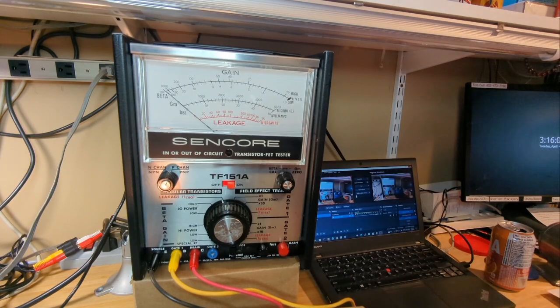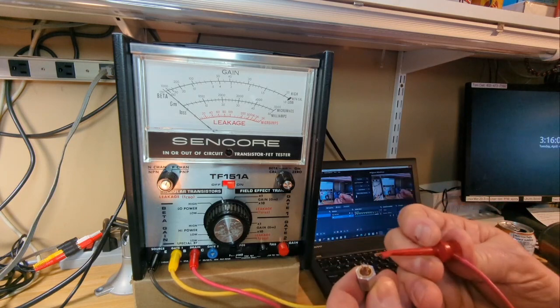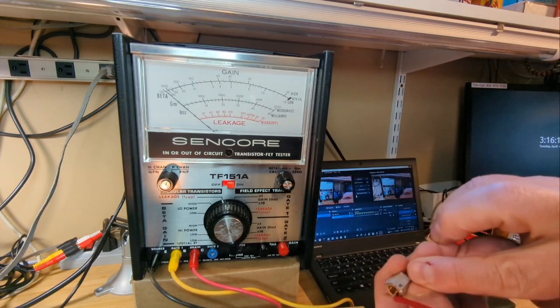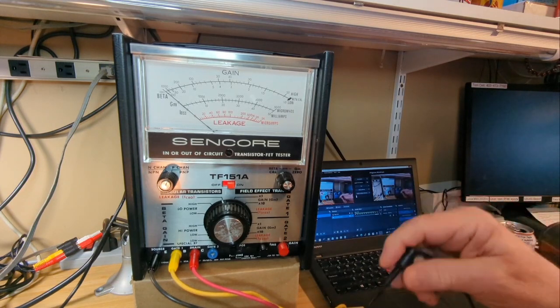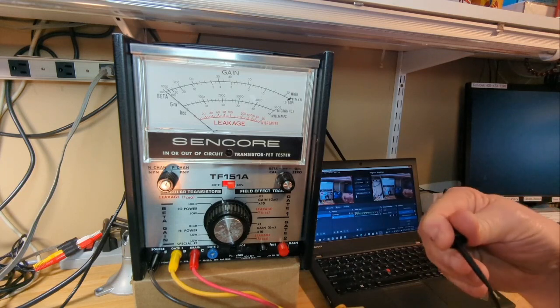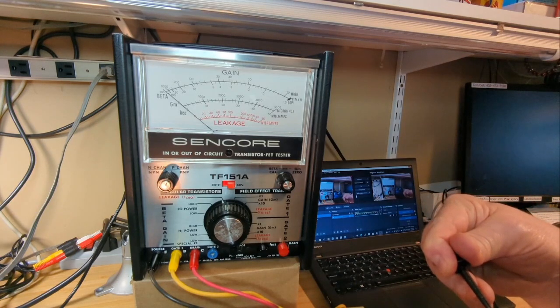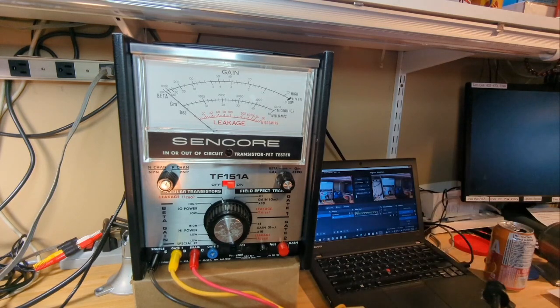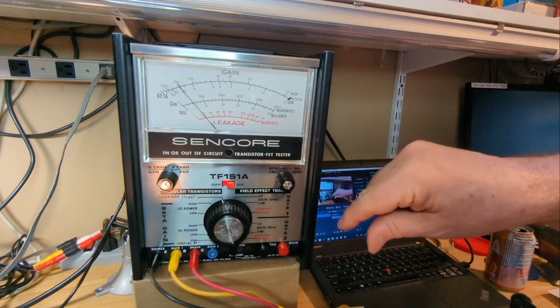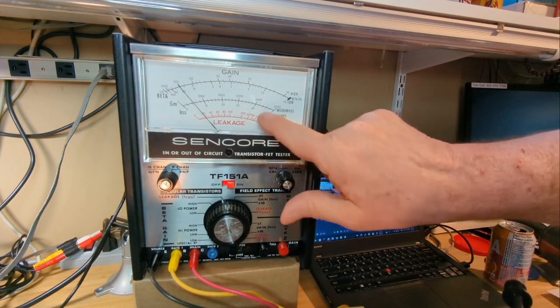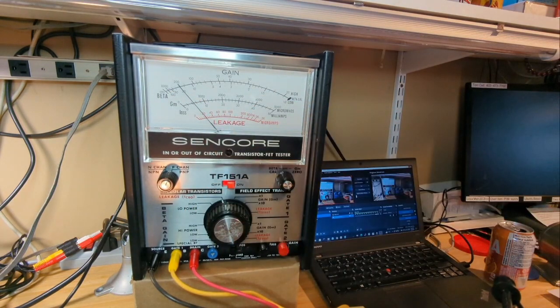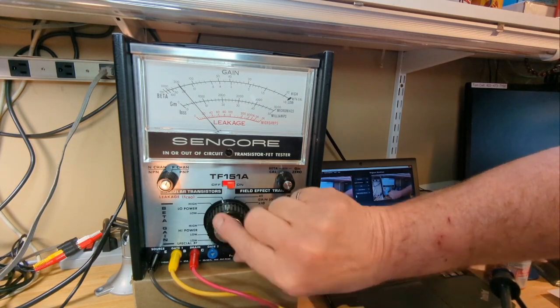How about this transistor? Might as well test this one as long as we don't know. Maybe it is bad. So we'll connect again the collector to the collector. It's so nice to write things neatly on components and placement in the device so that you can reference it while you're troubleshooting and not go back and forth to a data sheet. Okay, so we're going to hook this up in the leakage mode. Oh, look how low the leakage is. It's 20 microamps. You can already see the other one pegged the meter. And by the way, the maximum leakage, according to the setup book, is 50 microamps. So this fellow is doing quite well for us in the leakage department.